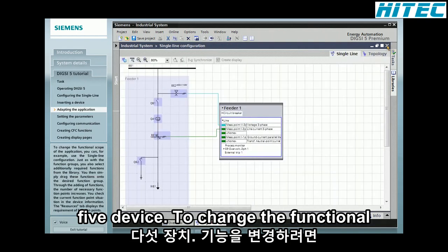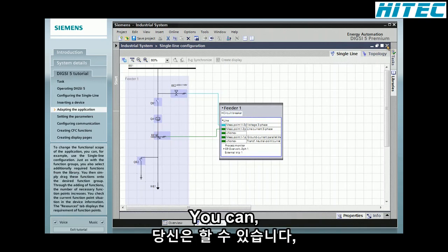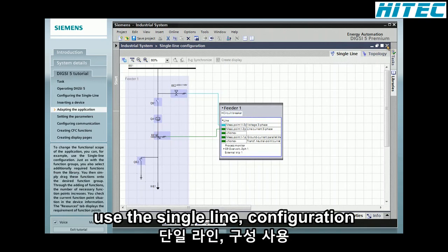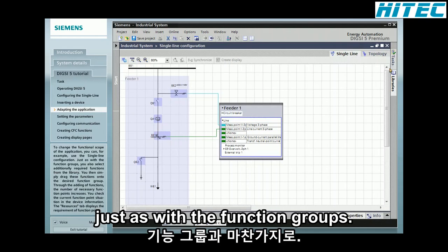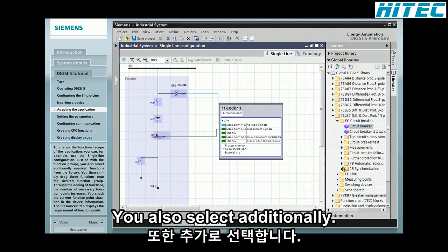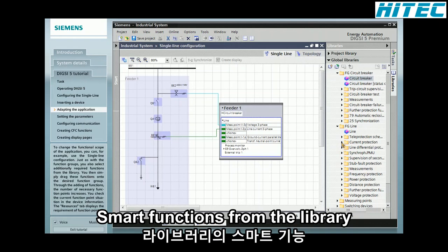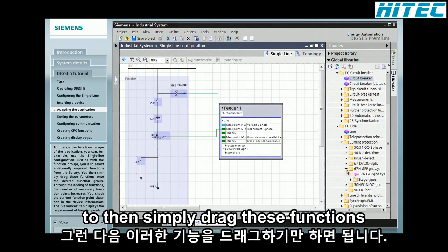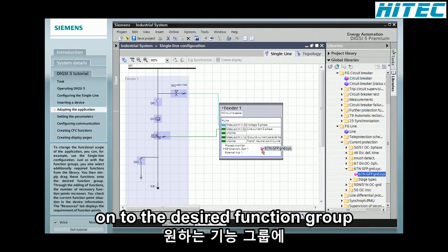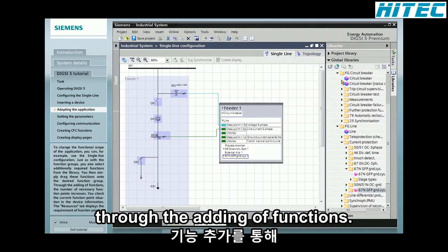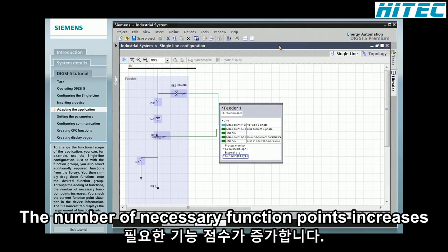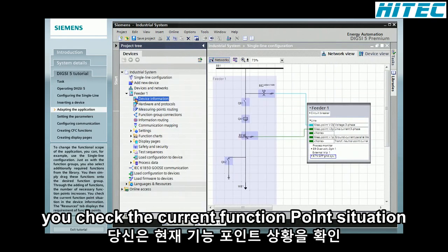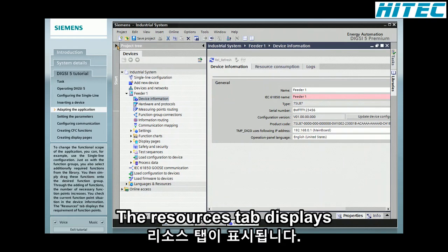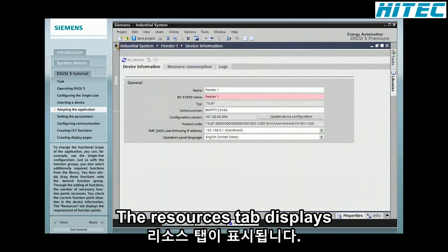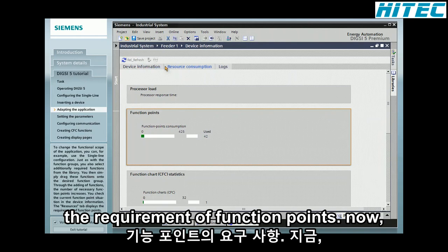To change the functional scope of the application, you can, for example, use the single-line configuration. Just as with the function groups, you also select additionally required functions from the library. You then simply drag these functions onto the desired function group. Through the adding of functions, the number of necessary function points increases. You check the current function point situation in the device information. The Resources tab displays the requirement of function points.